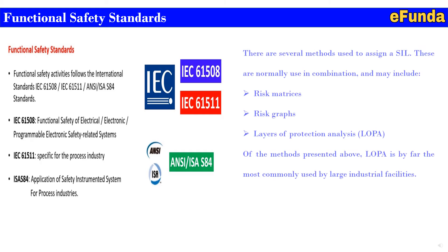Several methods are used to assign a SIL. These are normally used in combination and may include risk matrices, risk graph, and Layer of Protection Analysis, that is LOPA. Of these methods, LOPA is by far the most commonly used at large industrial facilities. Understanding functional safety standards is very important when implementing a SIL system or safety-complied system for plant operation and certification.